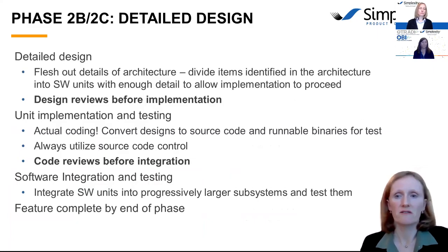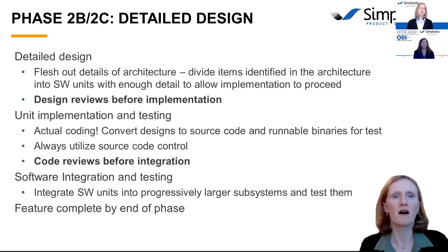So during detail design, which is the largest of the product development phases, we'll flesh out the details of the architecture from phase 2A. So we take those high-level software items, break them into units, and design and document enough detail to allow implementation. Before implementing the code, a formal design review must be held and documented.